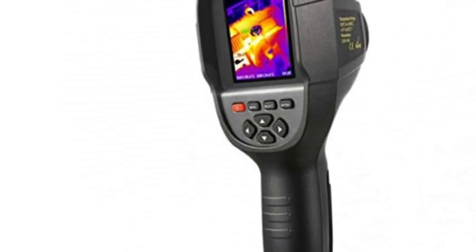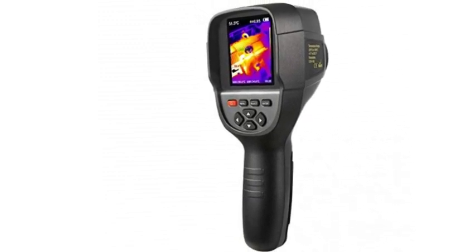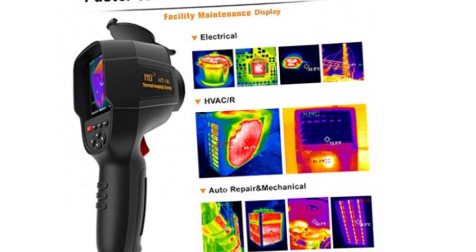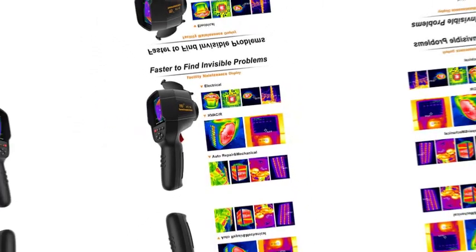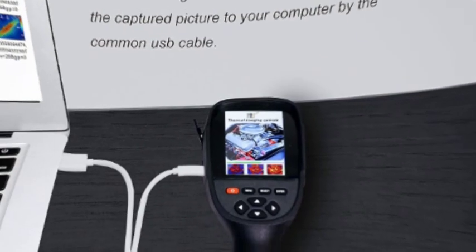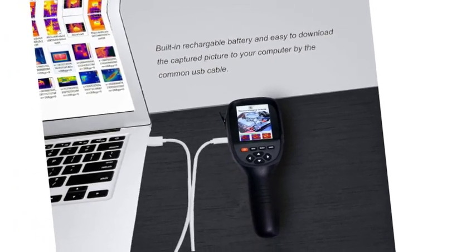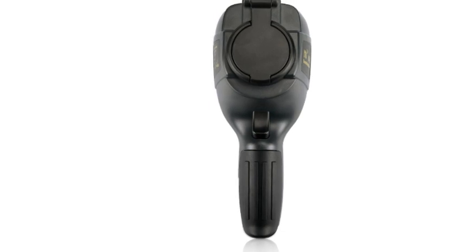The number 4 on the list is the Tools for Instrument Infrared Camera. Infrared thermography is a powerful, non-invasive, safe way to let you see heat patterns, reliably measure temperature, and store images for instant troubleshooting. The camera comes with high-resolution image quality — 35,200 pixels (220 x 160) infrared resolution, a 2.4-inch display screen, and 0.7 degrees Celsius thermal sensitivity. Measurement accuracy is plus or minus 2 degrees Celsius or 2%. This real-time thermal image camera provides 5 different color palettes: rainbow, iron oxide red, cold color, white heat, and black heat, for a better, more detailed display of the target. Multifunctional application for almost every maintenance application within an industrial or commercial facility, including electrical, HVACR, mechanical, and facility maintenance predictive maintenance.